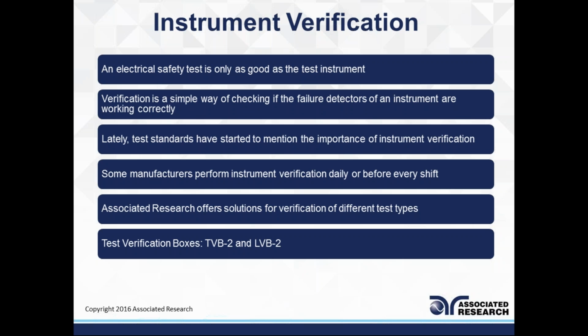In the past, there was never any emphasis on instrument verification. However, being in the industry, we have seen a slight change in trend where some standards are starting to talk about verification. There are some UL standards, or some excerpts in the standards, that talk about verification of test instruments. Verification could be a daily routine or daily practice. It could be more than once a day, for example before every shift.